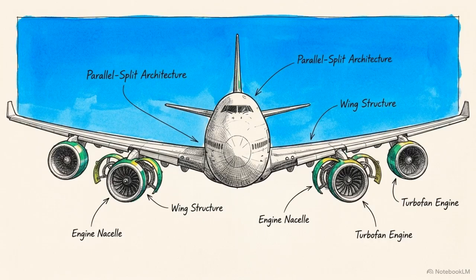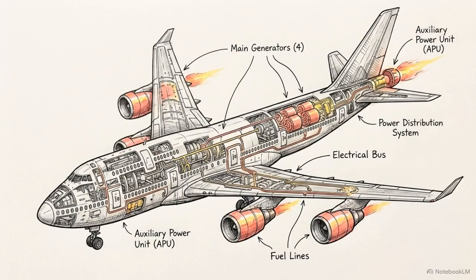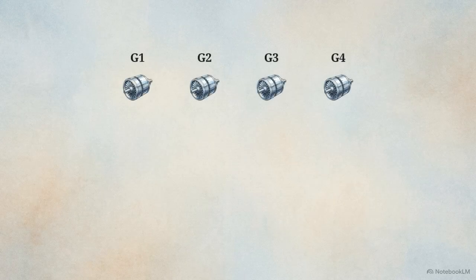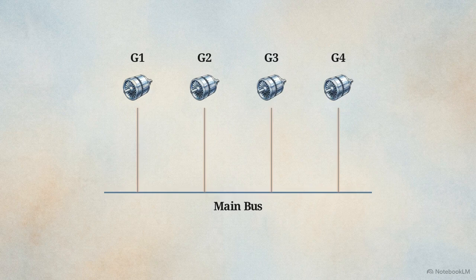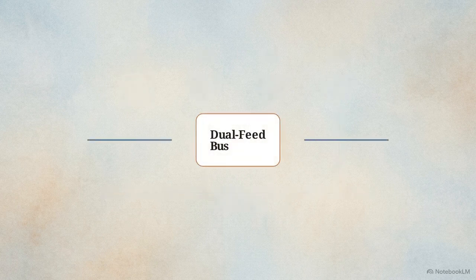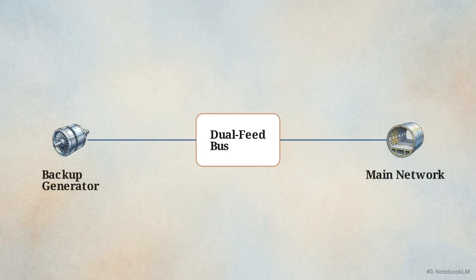Larger aircraft require a different approach. A Boeing 747-400 utilizes a parallel split architecture to handle its massive electrical demands. With 4 engine-driven generators, plus an auxiliary power unit in the tail, the routing logic here is intensely complex. In this schematic, all 4 generators actively share the load. If generator 1 fails, the system instantly splits and dynamically reroutes power from the remaining engines. To ensure critical components stay powered, dual-feed buses receive redundant power lines from entirely different sides of the network.